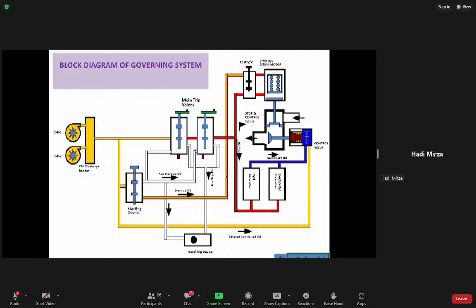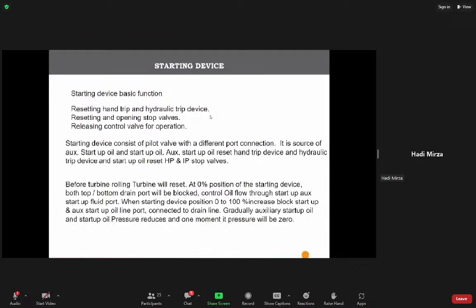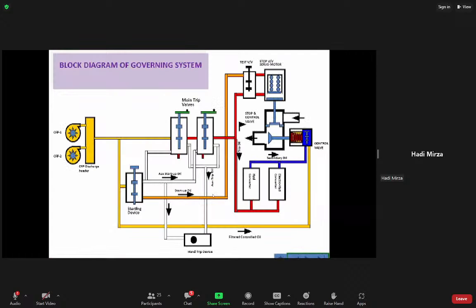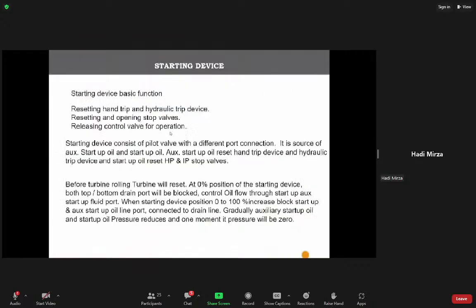We will see what the starting device is. A basic function of the starting device is to reset the hand trip and hydraulic trip devices. The hand trip valve is the main trip valve here. Hydraulic trip devices are the overspeed trip release device and the vacuum trip device in 250 megawatt or any other governor system. Resetting and opening stop valves. Here you can see the starting device will reset the stop test valve and in turn reset the servo motor of the stop valve. Releasing the control valve for operation.